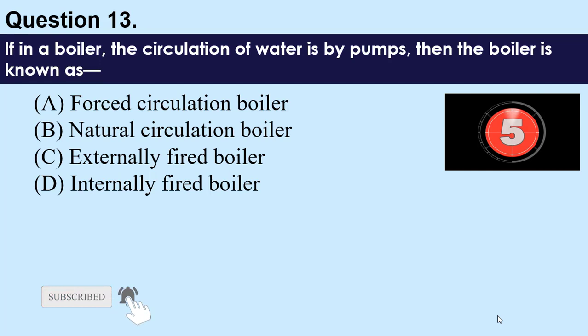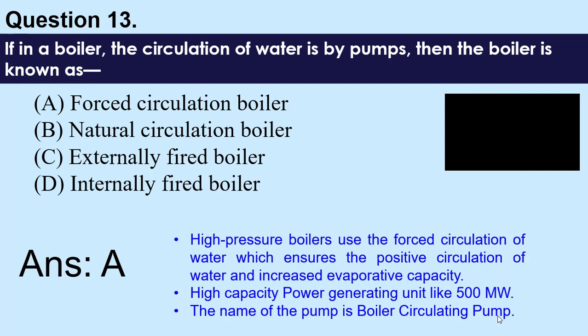Question number 13: If in a boiler the circulation of water is by pumps, then the boiler is known as — A) force circulation boiler, B) natural circulation boiler, C) externally fired boiler, D) internally fired boiler. The answer is A — force circulation boiler. In high-pressure boilers, forced circulation ensures positive water circulation and increased evaporative capacity. In high-capacity power generating units of 500 MW and above, forced circulation is used, and the pump is called a boiler circulating pump.